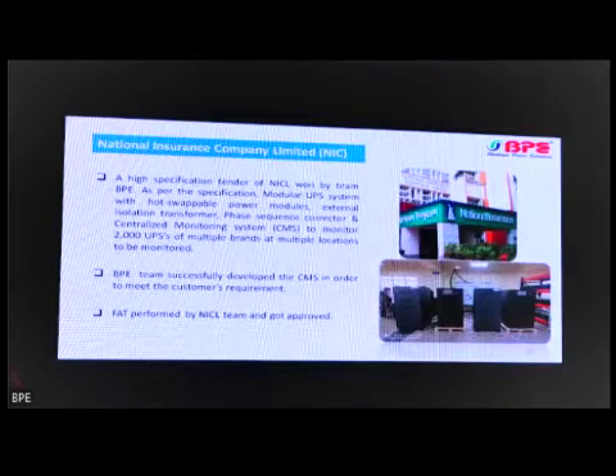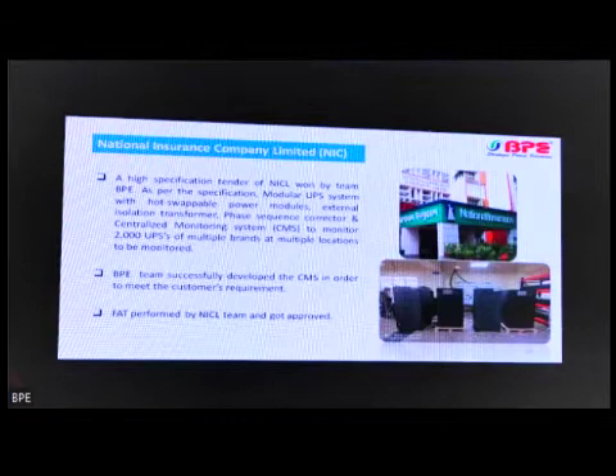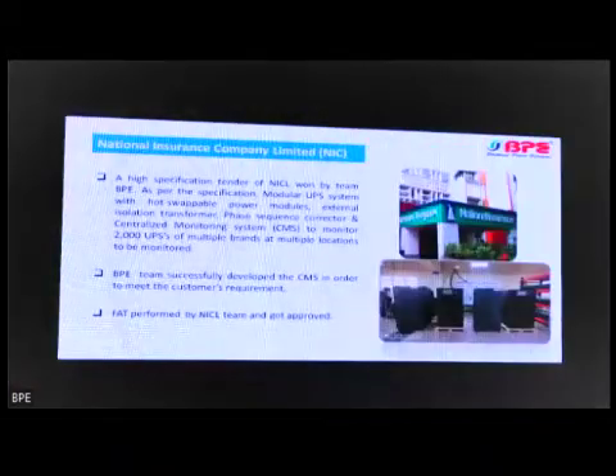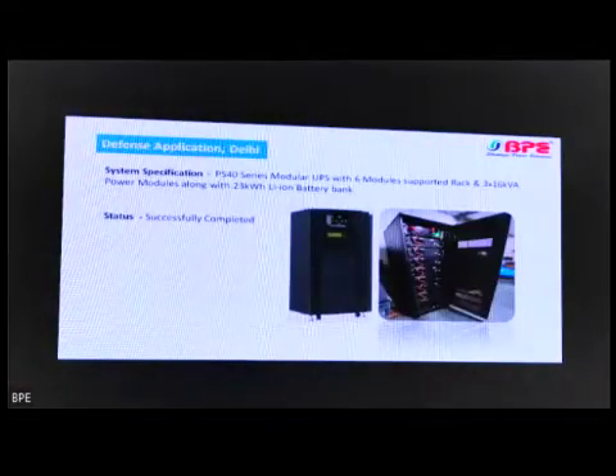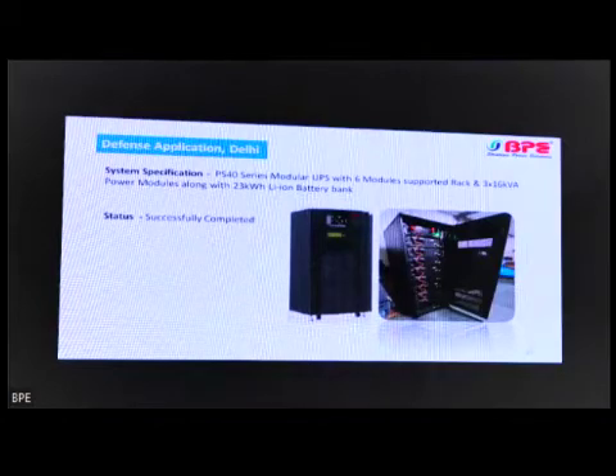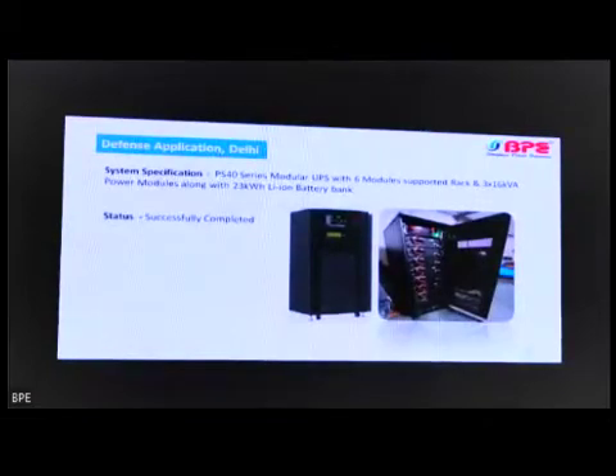Then NICL, a high specification tender, was won by us. As per the specification, it required a modular UPS with hot swappable power modules, external isolation transformer, phase sequence corrector, and a centralized monitoring system, CMS, to monitor 2000 UPSs of multiple brands at multiple locations all across India. So we provided them a CMS to meet the requirement, and the FAT was confirmed by NIC and got approved, and we supplied this successfully. It has been installed also.